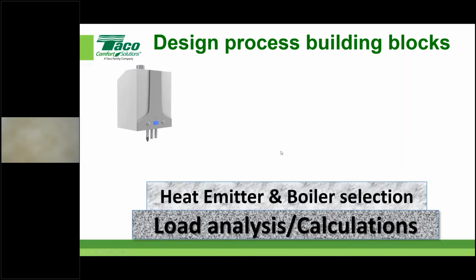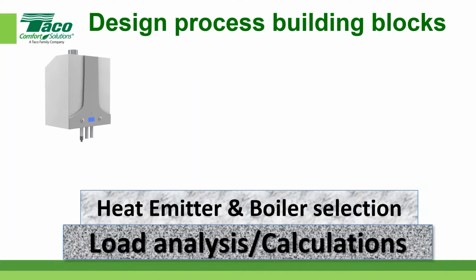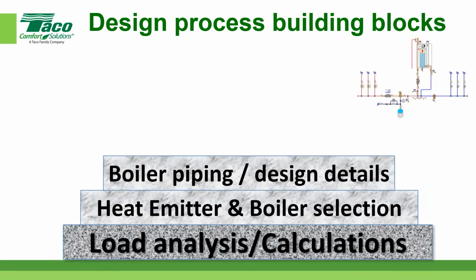Appreciate that. So once we figure out what the loads are and we do those calculations, then we can start selecting the type of heat emitter, and a lot of times the type of heat emitter will drive the style of boiler. For instance, if I'm doing a radiant floor application, with a lot of low temperature things, then my boilers make sense to be a condensing piece of equipment. And nowadays I've got to throw this out there, maybe a ground source or an air to water heat pump, because those all require lower supply water temperatures. So those are things to think about.